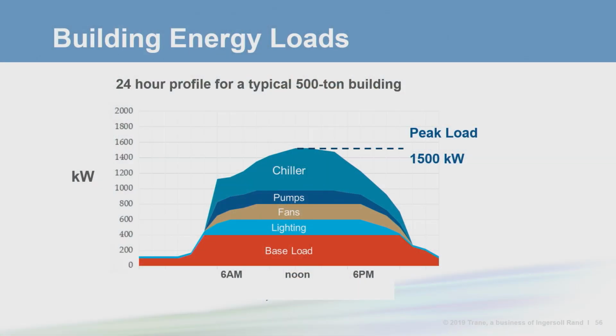Here is the energy distribution for a typical 500-ton building, showing the energy contribution from the various loads over a 24-hour period. The bottom four loads, the base, lighting, fans, and pumps, are all the electrical loads. The remaining chiller portion is considered a thermal load. From the distribution, you can see that the thermal loads make up around 30% of the total building's peak load.